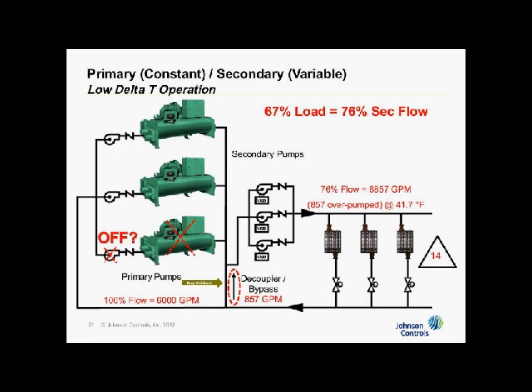The second thing that's happening here is the only way in which I can keep that backflow from happening is to turn on this pump, this pump that was off. Well, I can't turn it off. I've got to leave it on. And if I leave it on, I've got to turn on this chiller, or I pump a dead chiller and just pump 54 degrees directly over into 40, which we don't want either. So you are forced, because of low delta T, to run 3 chillers to do a 2-chiller job. Now that in itself is not a bad thing, because you remember myth number 1 from last time.